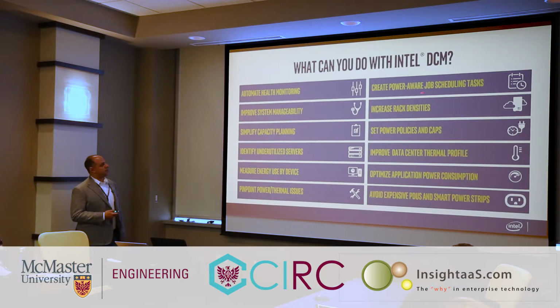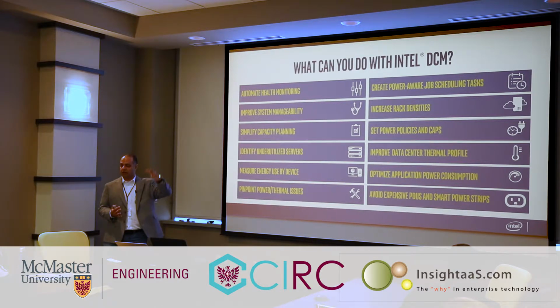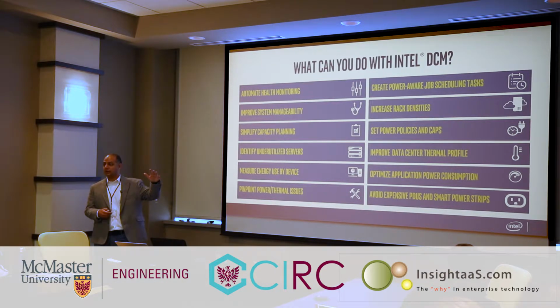Another thing is being able to increase workload rack densities, right? So not just adding systems, but figuring out, not depending on your derated power, but using the historical data that DCM collected over time to understand the actual utilization or power consumption of these devices, and therefore rack and stack accordingly, right? I'll talk about that also.